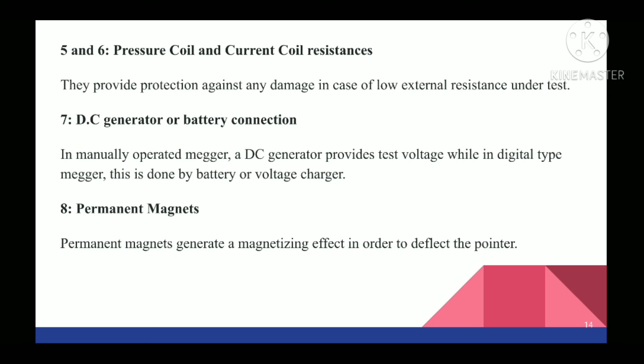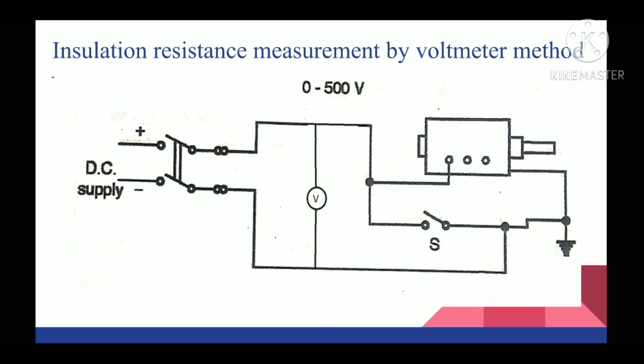The next method is insulation resistance measurement by the voltmeter method. In this diagram you can see there is a DC supply, next is a voltmeter having a range of 0 to 500 volts, and the connection is made to this motor by using this switch. This method can be used when a Megger is not available.